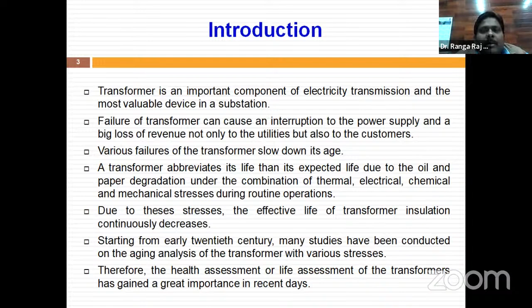In any electrical machine, insulation is the heart. If insulation works effectively, performance is also very well. So we should focus more on the insulation, oil and paper. Paper provides insulation between electrical parts, and we wrap the paper on the winding. Once the winding is heated, the paper absorbs the heat first, and the remaining heat is absorbed by the oil.